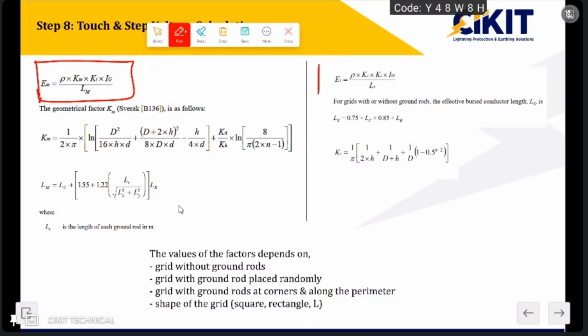Similarly, the actual step voltage can be calculated by using this formula. So for the different parameters involved, the standard has mentioned the procedure for calculating them also. So Km they have provided a formula, Lm is the length of the grid mesh conductors we are using, and the values mainly depend upon different parameters. One is whether we are providing ground rods for this grid or not. It is not mandatory to provide earth rods for this earth mat. Even if no earth rods are provided, the design can be considered as safe if the step and touch voltages are within the tolerable limit.